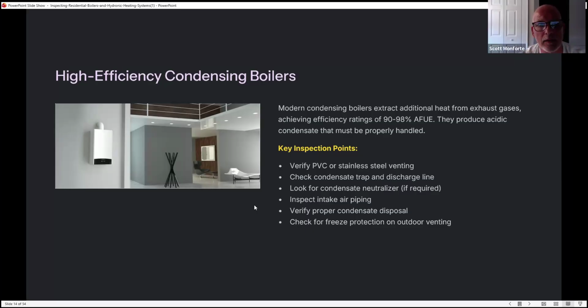And that's the same thing with a water heater. I've talked to so many different guys. It should be piped to the outside. So if you see any one of these condensing boilers and they have the little pipe sticking out on top because they're being lazy, I mean, the manufacturer wants to see it piped outside, taking air from the outside. You'll get some guys who say it creates condensation and rust on it, but they should be piped outside. And in one of our pictures, you'll see the exhaust. They'll use Schedule 80, which is the gray stuff, and then they'll use PVC for the intake, and they use both. It's acceptable, but that's how I usually tell. I mean, if it's got PVC pipe, it's condensing, whether it's a water heater or a boiler or a combination boiler hot water unit. Okay, great.